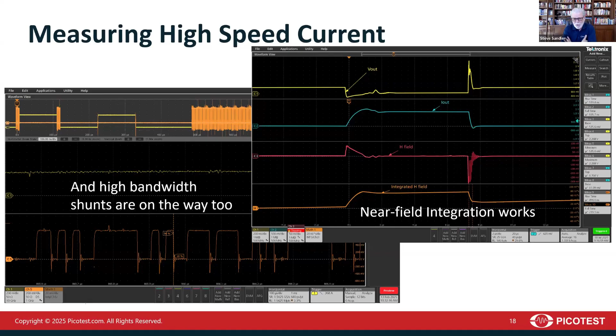And that's what this picture on the left is in the bottom trace. That's actually the voltage across one of our very high speed shunts in our high speed load transient. We also need to be able to float these measurements, and since TICP offers 100 dB common mode rejection, actually even better than 100 dB, it means that we can measure floating measurements, including high side gates, and our current shunt resistors are actually floating. And so here you can see another picture of those floats.